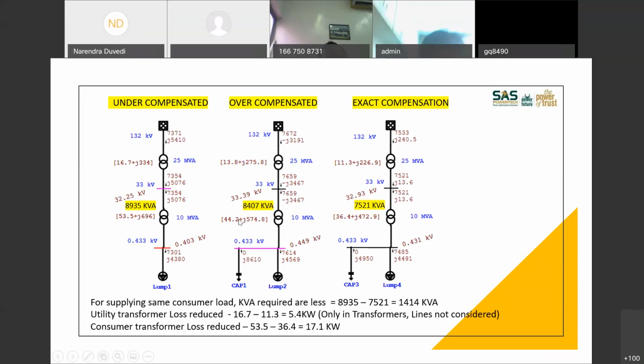Utility transformer losses also, if you see, in the first case are 16.7 kilowatt, in the last case they were 11.3. So 5.4 kilowatt are saved as far as the utility is concerned without doing anything by them. Just if the consumer controls the power factor at unity, they can save about 5.4 kilowatt. So again, it's a net saving, because these 5.4 kilowatt they have to pay to the transmission company from where they get this supply. So that also can be saved. So this was the basic idea behind controlling power factor at unity at the consumer's end, and this is a technical explanation for all that.